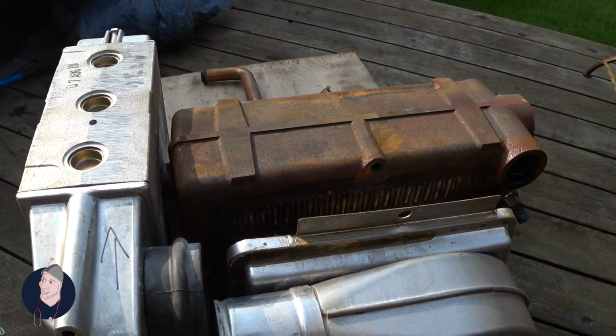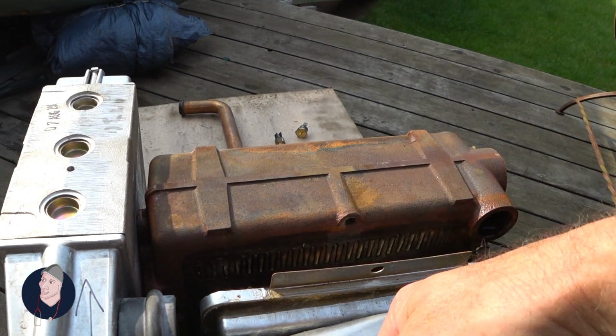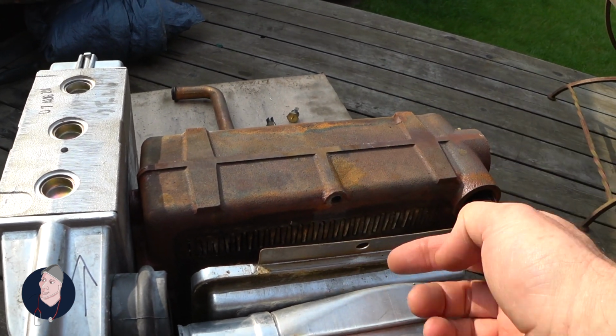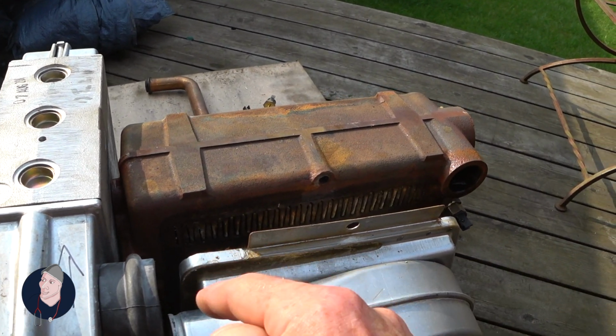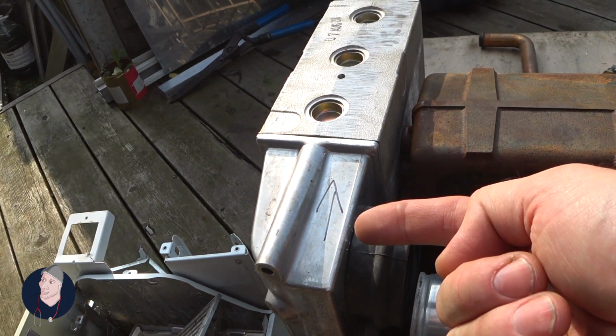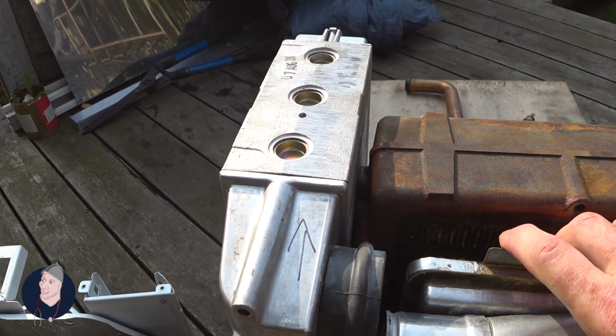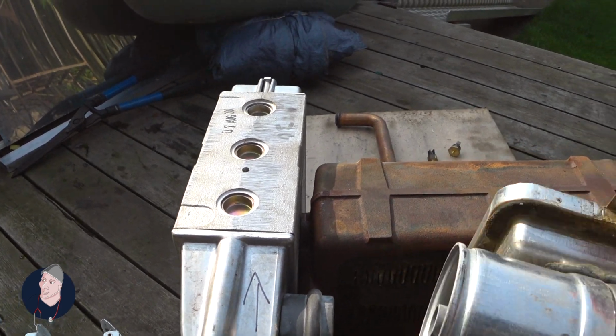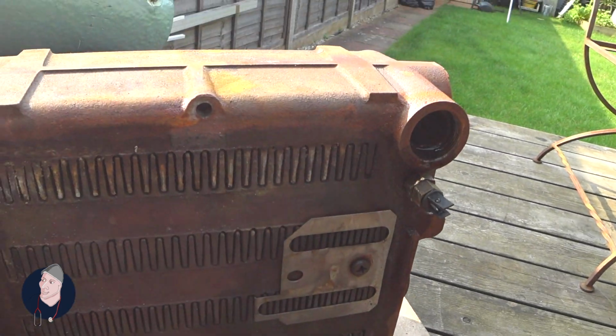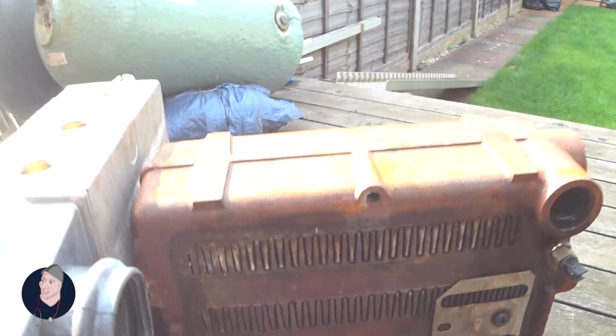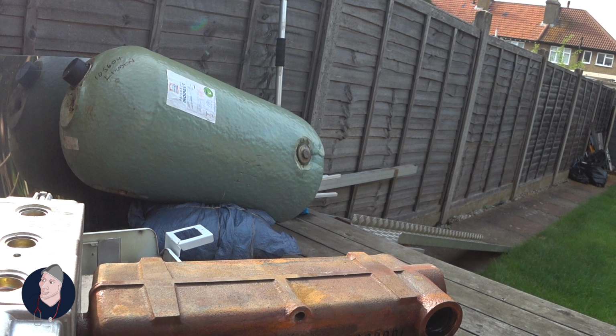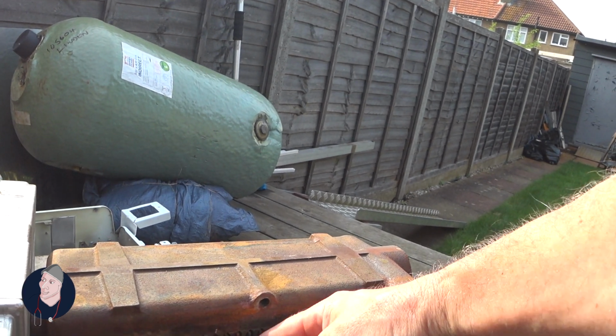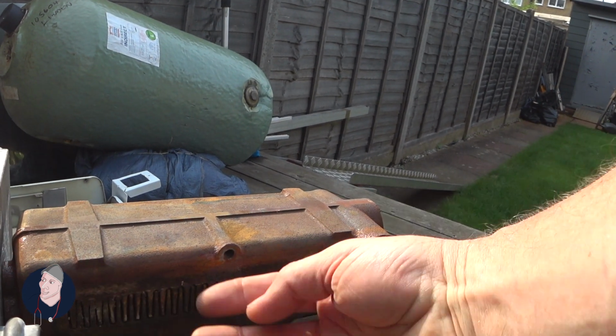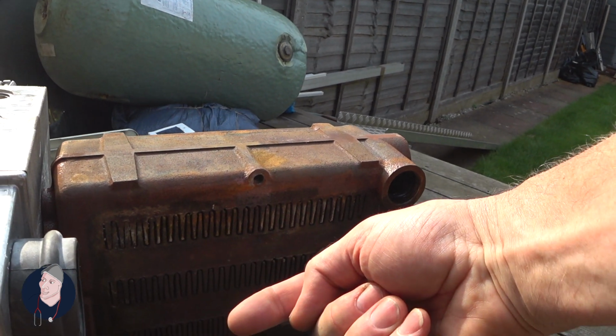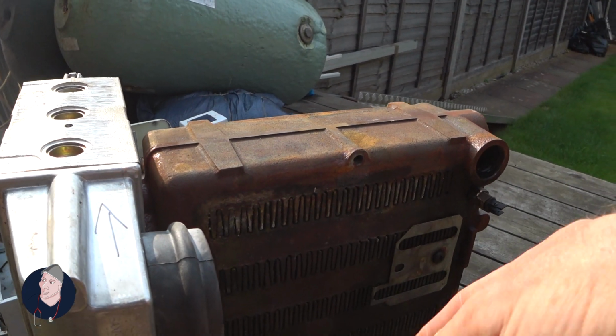if you imagine when the fan's running, it's drawing hot air through the heat exchanger, through here. That hot air is then passed through the secondary heat exchanger. So if we move this out of the way, you can see the top fins of the main heat exchanger. From here, the air that is drawn through here is still hot. It still has some residual temperature left in it. So it then passes through this.